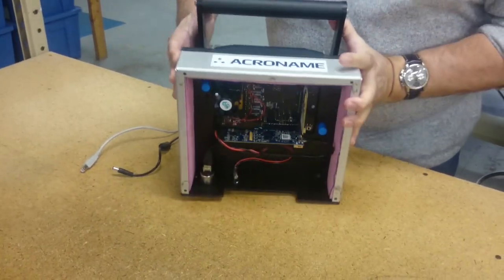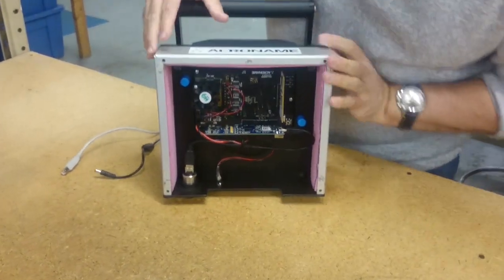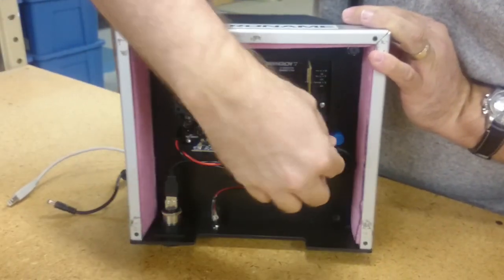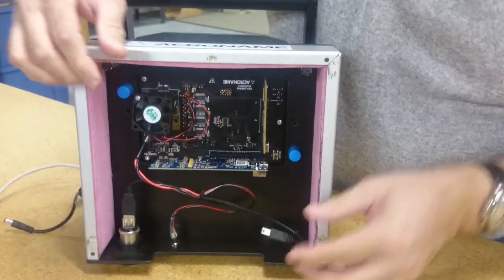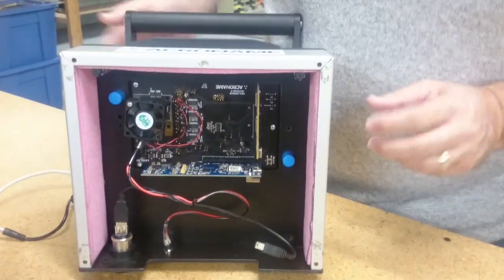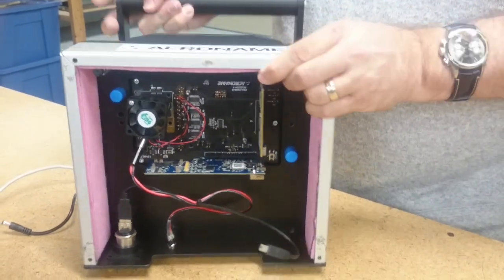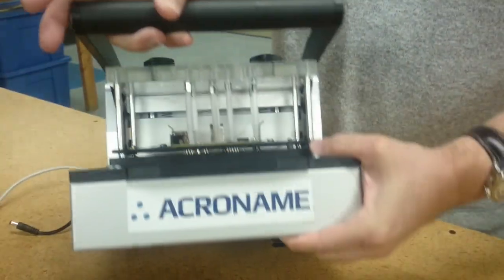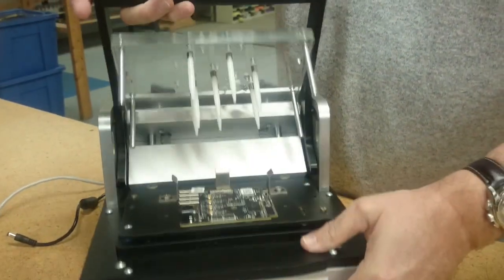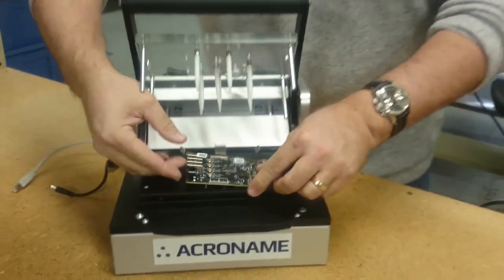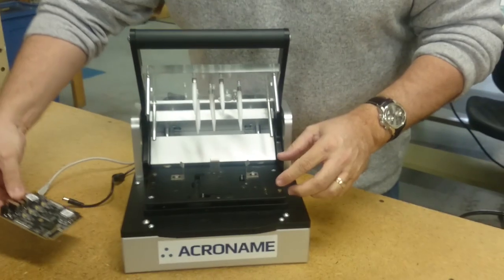After we unplug the fixture, we'll flip the fixture over and unplug the internal cables. First, we unhook power from the test point carrier board, and then we unplug USB from the MTM module. Now we'll pull out the ATS module.